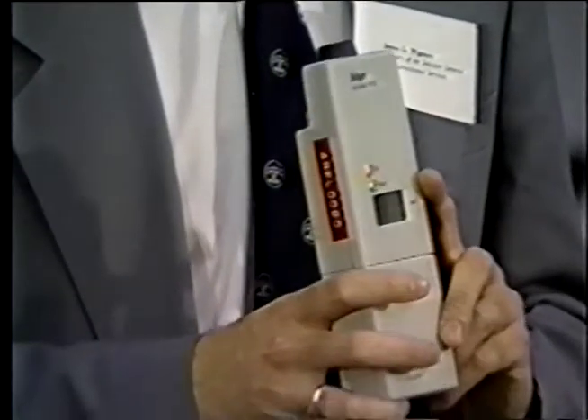The calibration of the Alcotest 7410 PA3 is the same as for the Alert, with a simulator solution to use, and it's calibrated to fail at 100 and above. The warn, or the Alert, is from 50 to 99 milligrams in 100 milliliters of blood, and the pass is 49 and below. So the levels are still the same no matter what device you use. They are all calibrated in Ontario to warn at 50 to 99 and to fail at 100 and above.